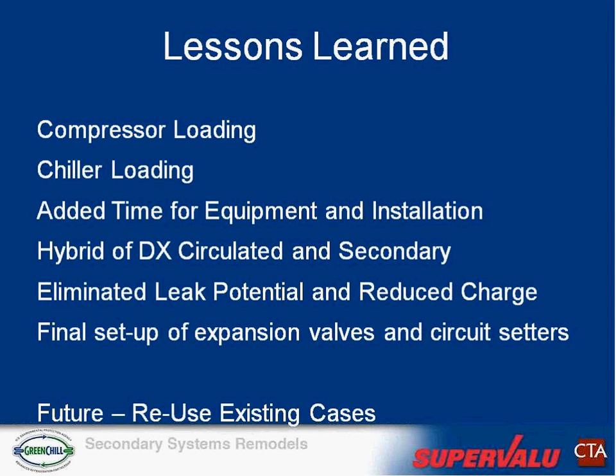So, getting into the lessons learned, to wrap it up, and then we'll see if we can get some thoughts from those involved. The compressor loading and the chiller loading, you have to think out at first. When we were first doing this, especially with the parallel racks, we had to think about whether we were going to bring on enough load to even get one of the chillers to operate properly. That was just working with the manufacturer and engineers going back and forth, and then getting with the contractors and letting them know how many cases we needed to start up at one time.